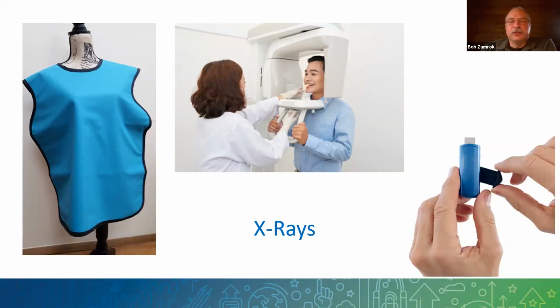Functionality is one thing, but with the 3D units now, you need to make sure that they're accurate. And the only way you're going to do that is a QA test. Every manufacturer sends a QA phantom for their 2D or their 3D units, and you need to run that through. And I've been working with the New York State inspectors because New York has changed their laws and they're going to change them again very shortly.